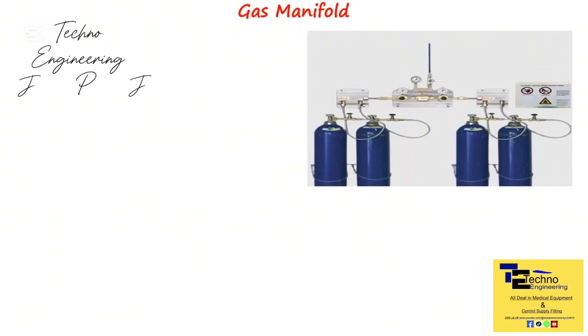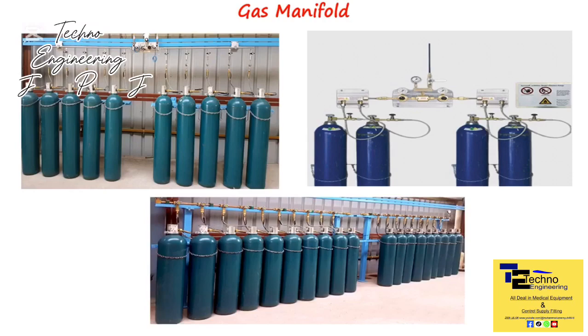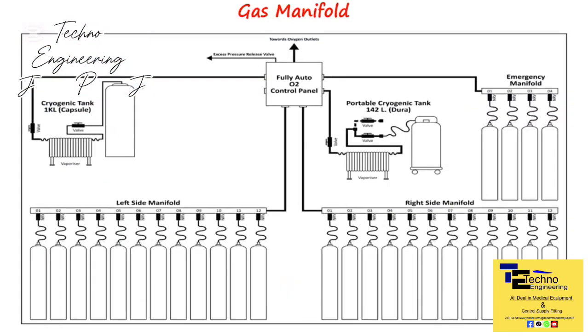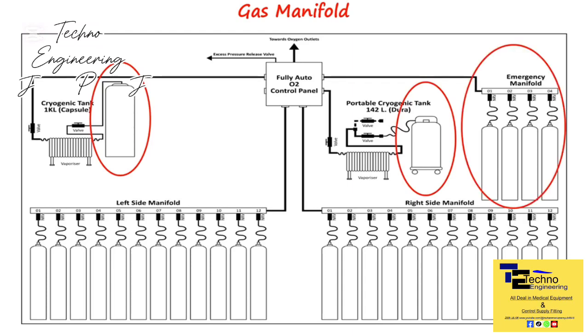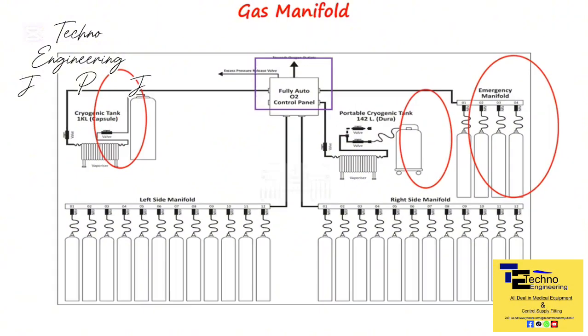A cylinder manifold is a system of large cylinders interconnected in series using pipes and valves, designed to supply gas through a pipeline system. Typically, the manifold consists of two-sided cylinder banks, and the number of cylinders connected can vary, ranging from 2 banks of 2 cylinders each to 2 banks of 20 cylinders each, based on facility requirements. It may also incorporate a liquid oxygen storage tank for continuous supply to the cylinder banks and an additional manifold bank for emergency situations.